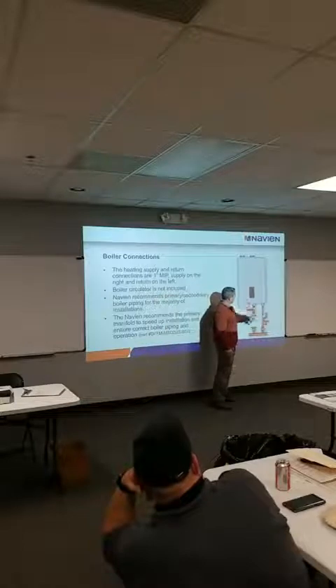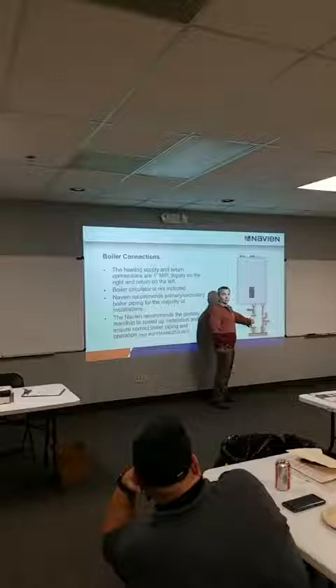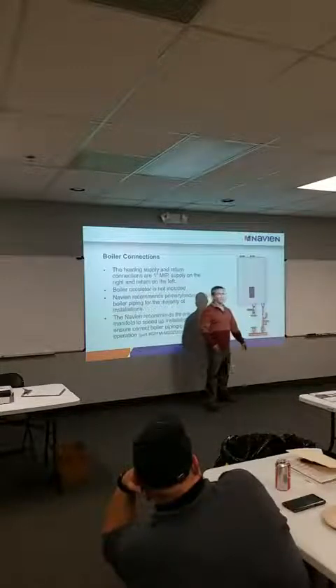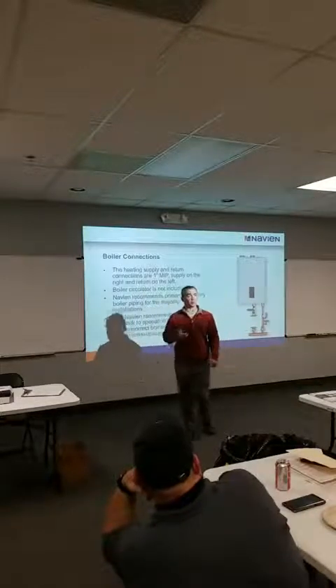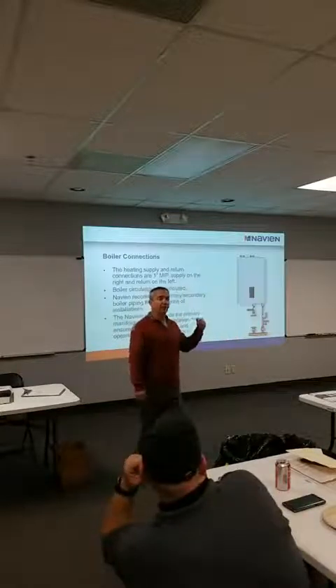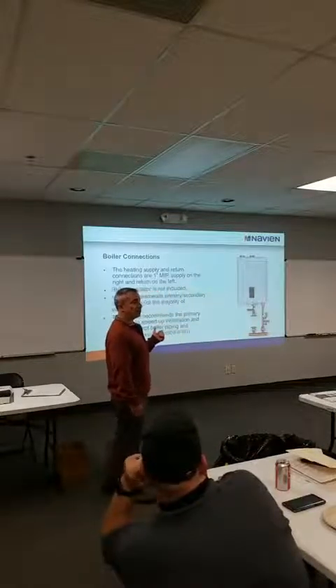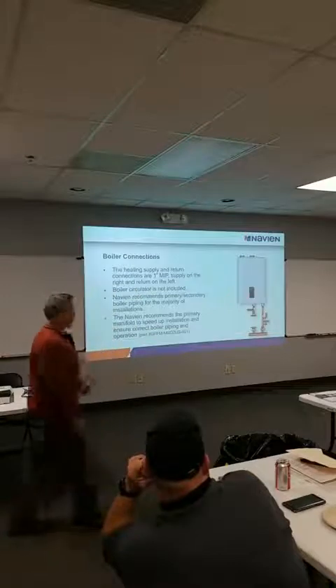The boiler manifold has a flange for your pump, and then in your manual, it'll give you pump specifications for our boiler. If you go to multiple boilers, you just don't purchase this manifold, you pipe it in sequence. The combi manifolds include our circ pump for the primary, so you don't need that flanged area for the manifold, so that won't be on the combi itself.